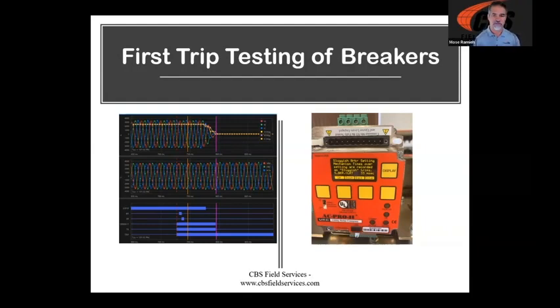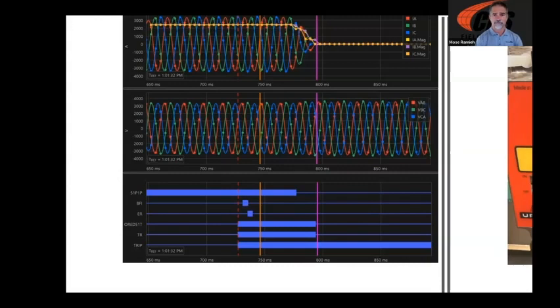Well, I mentioned that we could do timing tests, but when we do the timing test, we're actually taking that breaker out of service, and so we've actually operated it, right? We've moved the mechanism, we've kind of rolled all the bearings and everything like that. So when we go to do our timing test, are we getting a real image of how that breaker is going to perform after I've let it sit there for a while? And once again, we can do this both with test equipment, or we can take advantage of relays that we already have in our system. And once again, even using a fault event gives me a picture of how our breaker is going to perform in that first trip environment.